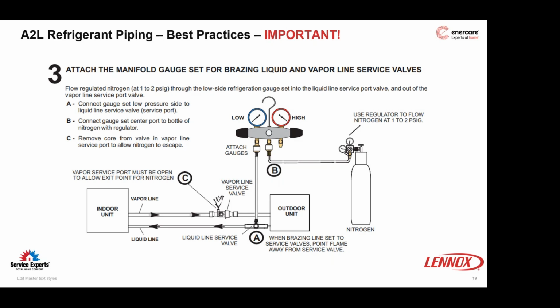Regardless, we're still using braze connections, so for the time being, it's imperative that nitrogen be connected to purge the line set before, flow low pressure nitrogen during, and purge the nitrogen to cool the joints after. Pictured is an approved connection method right out of the Lennox installation manual. Displacing oxygen while brazing has always been important, and with the introduction of the new A2L refrigerants, mildly flammable mind you, it is even more so now.